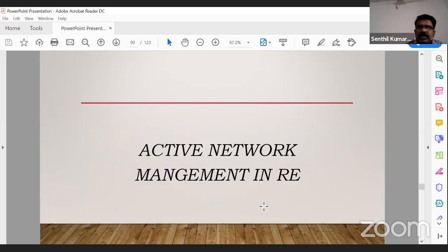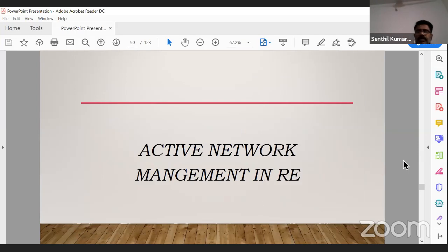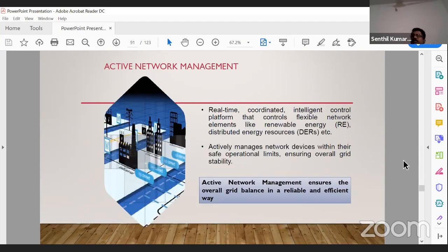This is AGC, and next we move to active network management in RE. In the next step, we introduce and establish active network management. Why active network management? Previously, for conventional power plants, we used automatic generation control. Active network management is for the renewable sector. Why only renewable sector? There, RE power has huge variation - it's a flex node, not a sustained load pickup generation. This is infirm power, and infirm power has a lot of huge variation.